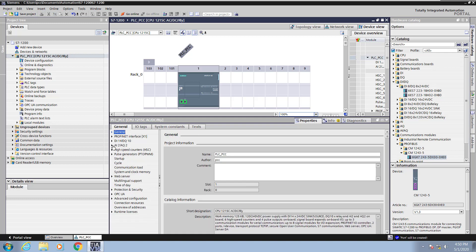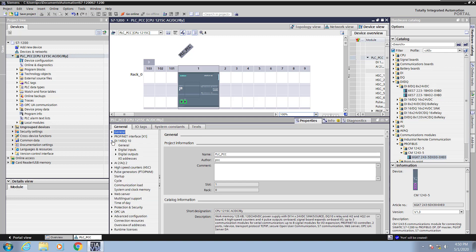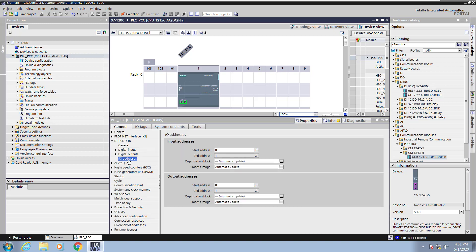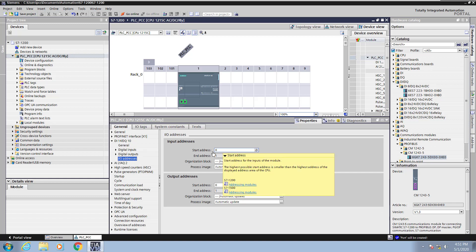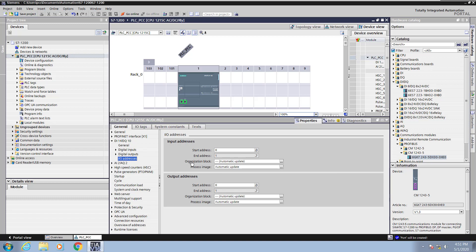Next I'm going to go and minimize the general area and look at the digital input area. I'm going to expand out the digital input area for the onboard I/O on the PLC. Now I'm going to select the I/O addresses area. This is where you can set the starting address for your input addresses and your output addresses. There are 14 digital input addresses so it's going to take up two bytes to accommodate all 14 digital inputs on the onboard I/O.